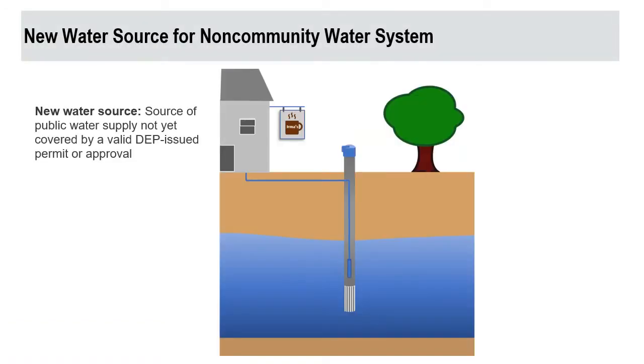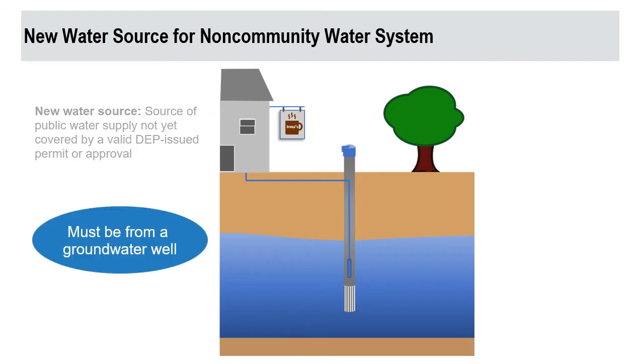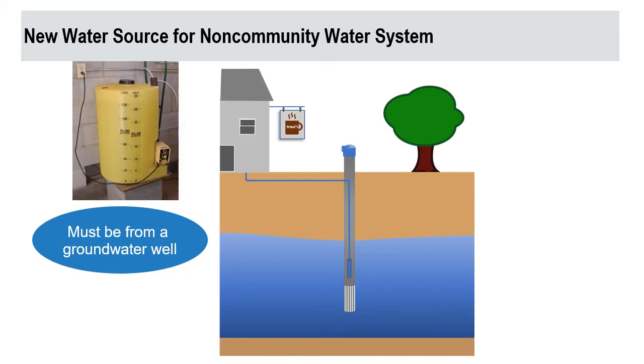A new water source is a source of public water supply that is not covered by a valid DEP-issued permit or approval. A new water source for a non-community public water system must be from a groundwater well. Dug wells, horizontal wells, springs, and surface water are not acceptable sources of water for the non-community water system application.